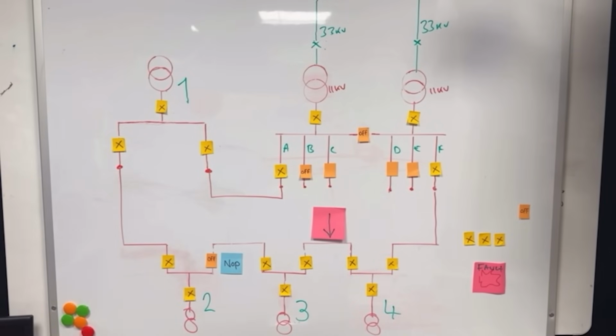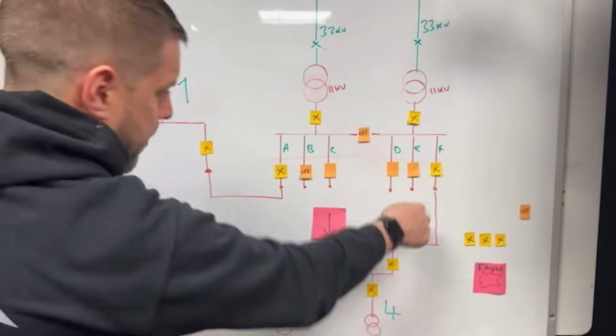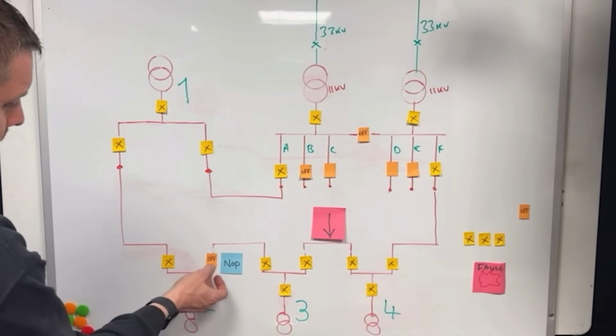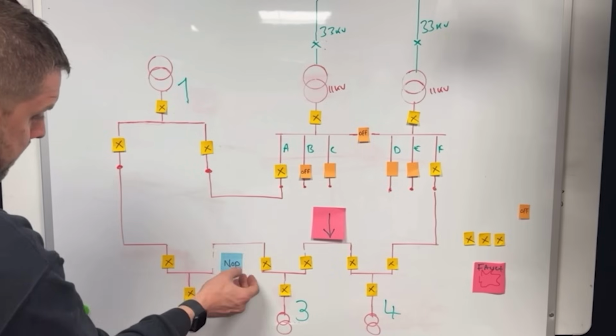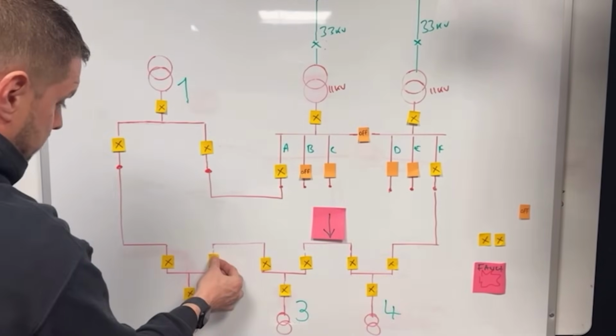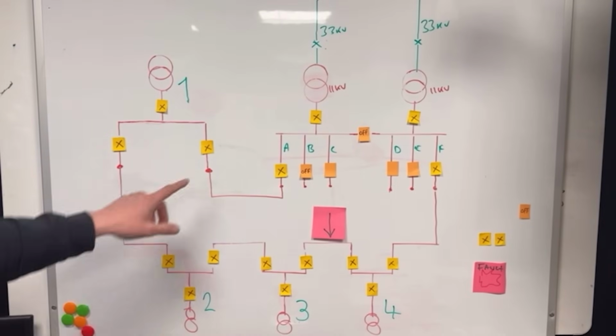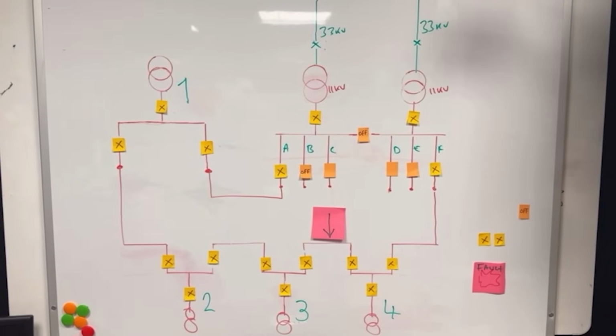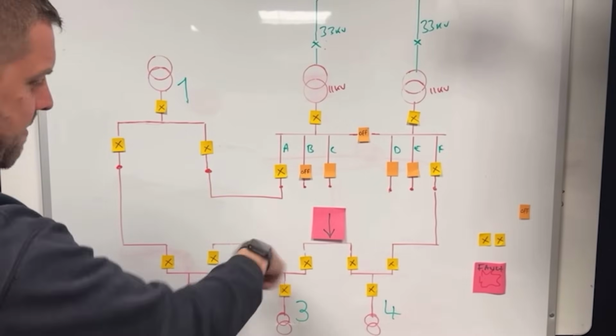Right, first of all, what we're going to do is close the normally open point, and close that breaker. So now we have an actual ring. Power is coming from that end, and going to that end. It's energised from both ends. Because of this, we have to make sure it's phased out, so that when you connect them together, L1 goes to L1, L2 goes to L2, L3 goes to L3. That's called phasing out. Now everything's live.